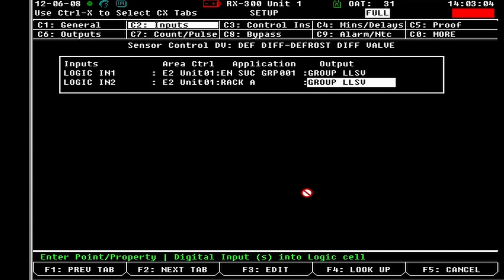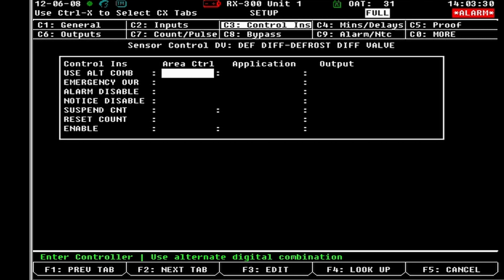So we're going to do an OR. So that way, if input 1 or input 2 is on, meaning it's calling for the group liquid-line solenoid or defrost differential valve in that group to be on, it's going to close and let that input energize and then control the liquid-line solenoid or defrost differential valve. So we got our inputs. So use alternative combo. So these are your other control ins. We're not using that.